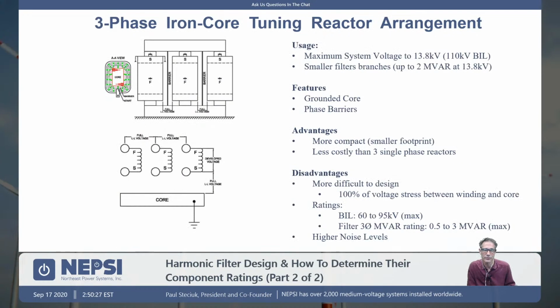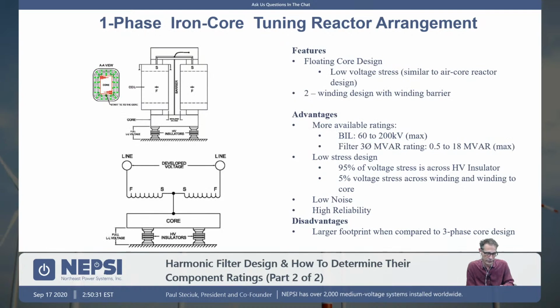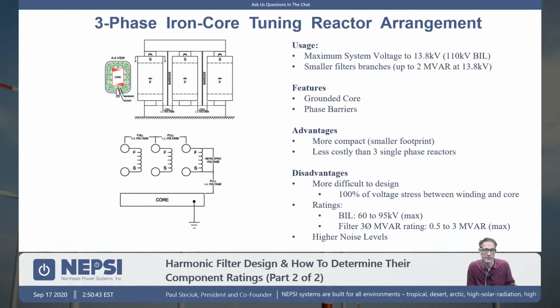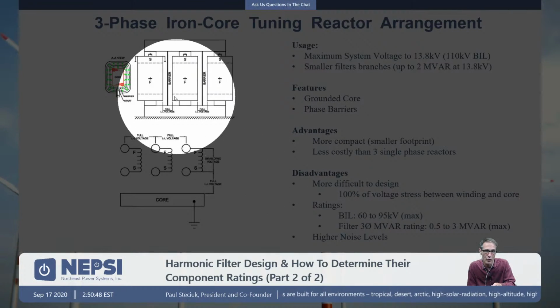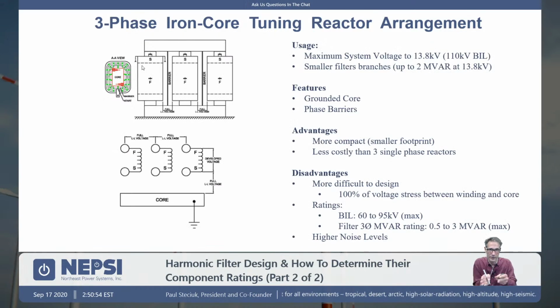So let's go through here. Three-phase reactors. The difference from single-phase reactors is that with single-phase we have just a single winding on the core. The core is elevated in potential, and it takes 3 single-phase reactors to make a 3-phase filter. When I go to a 3-phase reactor, I have a single core but 3 windings. So I have phase A, B, and C, and the inductance is formed between the 3 legs.